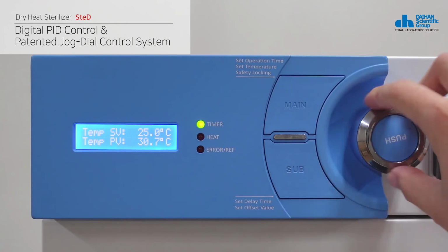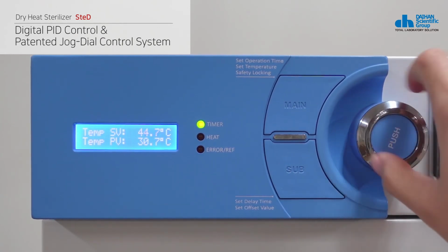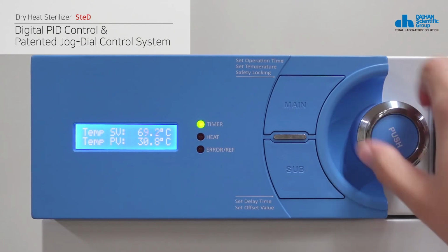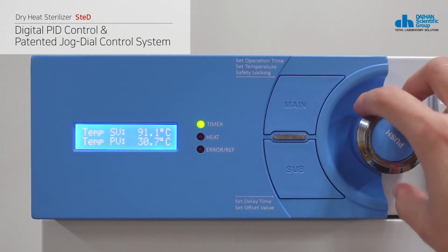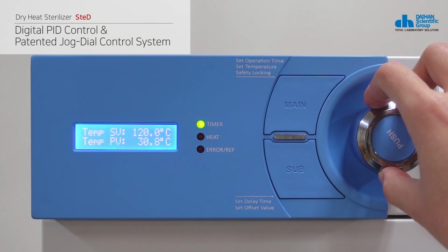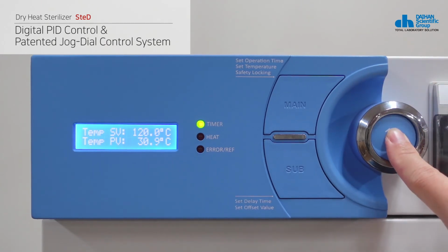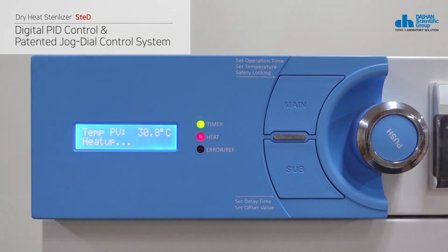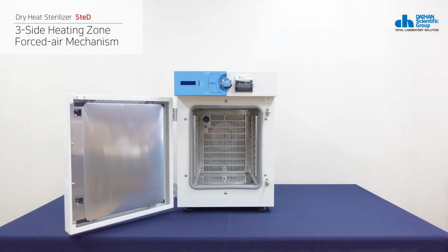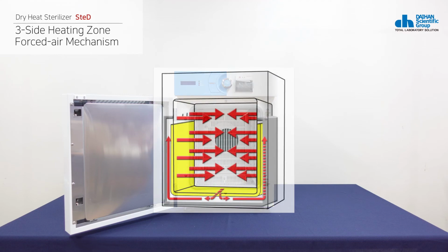The dry heat sterilizer of DAIHAN Scientific has achieved the best temperature accuracy and uniformity through digital PID control. In addition, the patent-registered jog dial has been adopted to maximize the convenience of adjustment. In a forced air circulation method, a powerful fan inhales air from the rear of the chamber and supplies it to a preheating zone surrounding 3 sides of the chamber, and the heated air moves uniformly and quickly into the chamber through the specially designed 3-side heating zone.